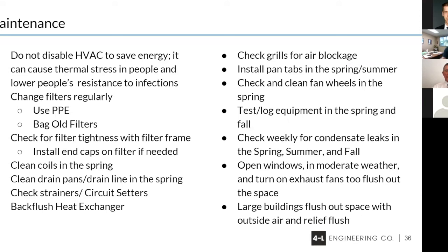I can't overstress maintenance on anything. First off, remember, always operate your system. You want to keep it operating so that it reduces the stress level on people and keeps the temperature and humidity in line. Change your filters on a regular basis. If you upgrade and you're using MERV 13 filters, understand that you're going to have to use some form of PPE. You're going to need to wear goggles, a face mask, and gloves. When you take the filter out, you need to bag the filter and throw it away at that point in time. Don't shake it. In the old days, we used to tell people, take the filter out and shake it. I'm sorry, you're collecting stuff now, and you don't want to shake it. You're just going to put it right back in the room.